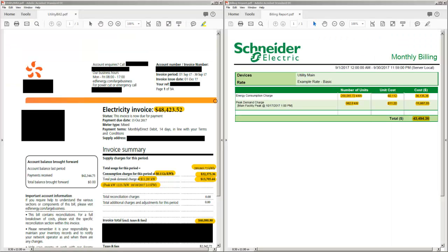Okay, so if you compare the bill that the EcoStruxure Power software generated and Susan's electric bill, you see a couple of discrepancies already. The kilowatt hour count appears to be different, and the fact that it's off by one digit causes one to suspect that it could be an incorrect meter read. Secondly, the peak kilowatt demand also appears to be a different value, and it happened at a different time. So both these discrepancies have resulted in a difference of almost $3,000.